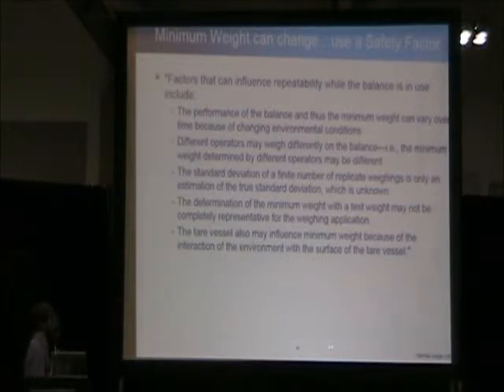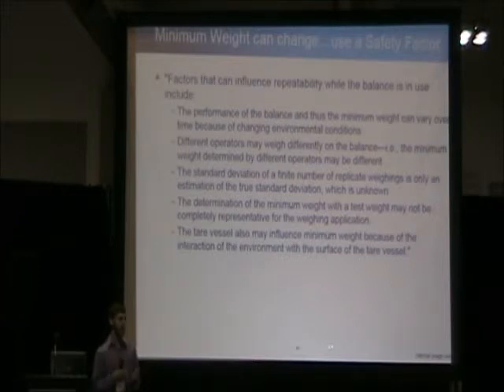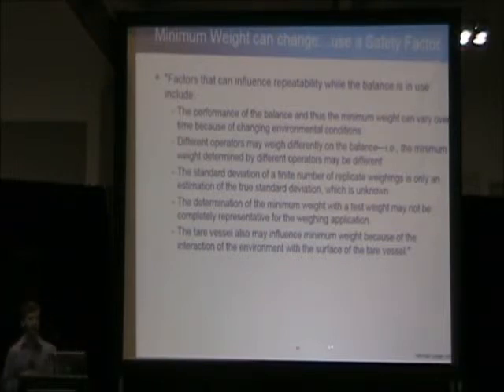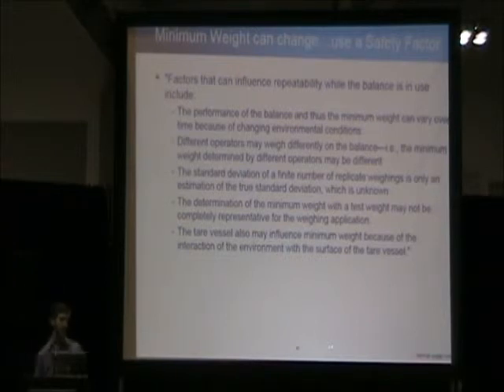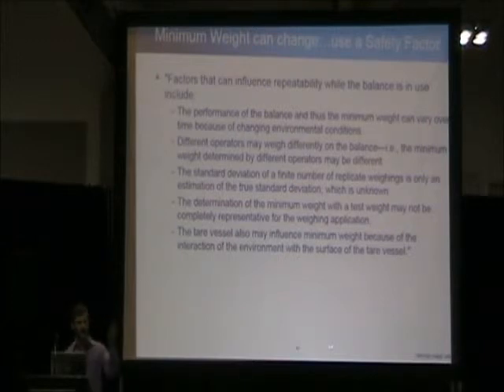The tare vessel itself also induces uncertainty of measurement. Weigh paper is very waxy and has a very high potential for static generation. Weigh boats are typically made out of plastic, and they also have a very high potential for electrostatics. Simply by putting a tare vessel into an analytical draft shield or a microbalance draft shield, you're going to be increasing the uncertainty of measurement.